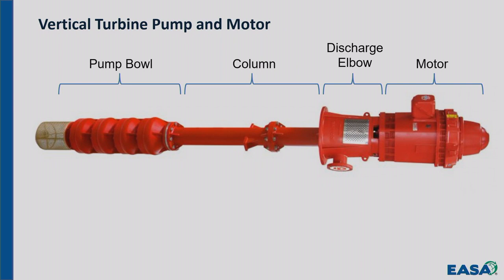The components: the pump bowl is the bottom part of the pump where the impellers and bowls are. The bowl is what they refer to as the stationary part of the pump. I'll just mention, it's just of interest, if it's got 4 stages and you take one of those, it's a pump bowl. If you take 2 of them and put them together, you still have a pump bowl. Put 4 of them together, you still have a pump bowl. That's the way the term is used. They use it for the individual stages, and they use it for the whole assembly. So you'll see that word pump bowl.